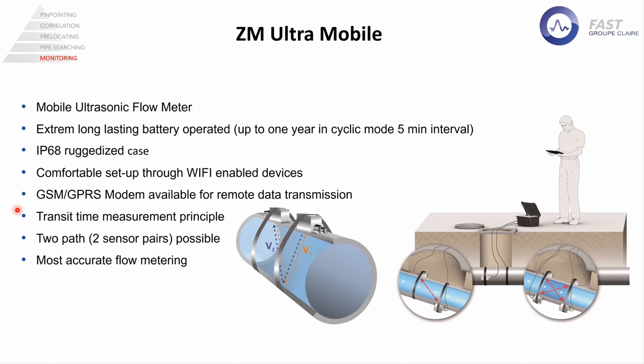The measurement principle is transit time, as you can see in the picture. That means it's a very accurate flow measurement calculation, based on the time deviation the signal needs to travel with the flow and against the flow. With the flow, you have a shorter transit time than against the flow. With this time deviation, you can calculate the exact flow velocity, and together with the pipeline cross-section, you can calculate the flow rate.